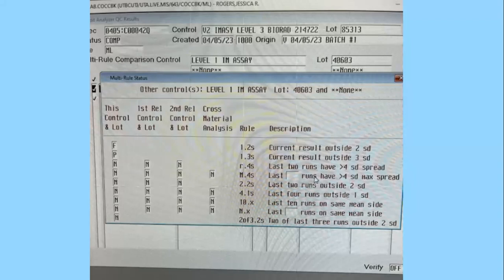The third option is to do the calibration and look at the QC level and see how full it is. If we do replace the QC, we'll just put replace QC. If we have to run it a fourth time, then we will just call maintenance and see if there is anything that we can do, or if there are other analyzers having the same problem. There's been cases where the flex packs haven't worked very well and they have been running low or high. Same with any other reagents that are put on the machine, can cause them to run a little low or a little high.